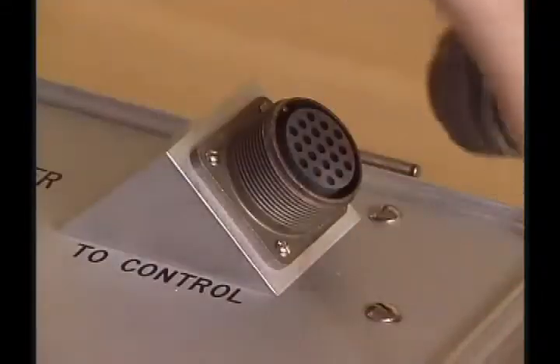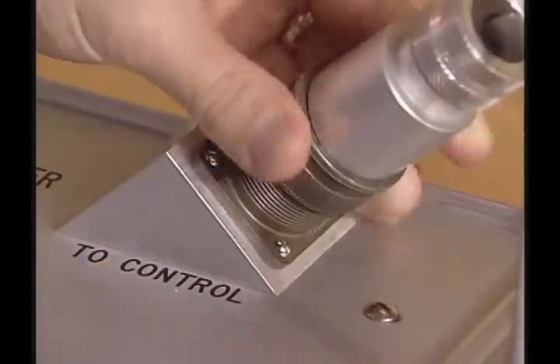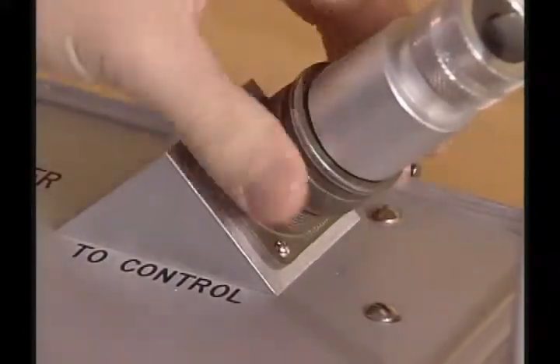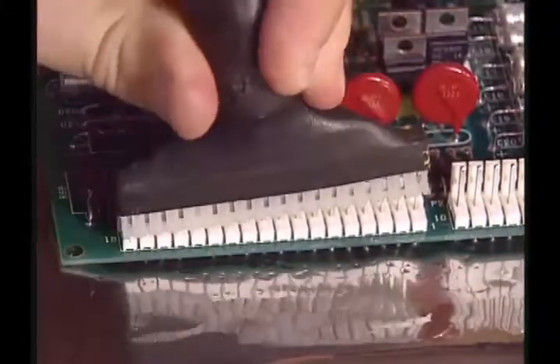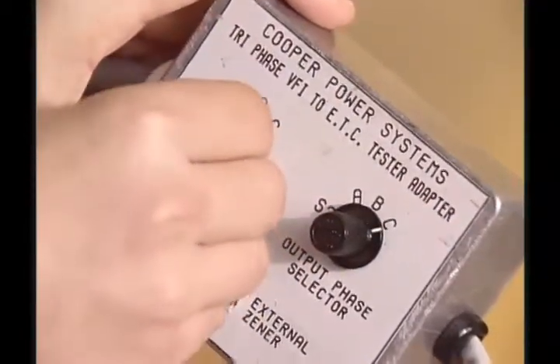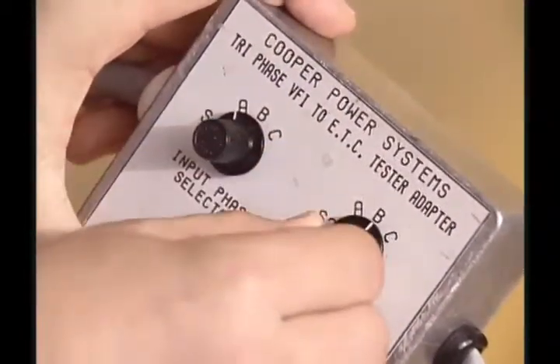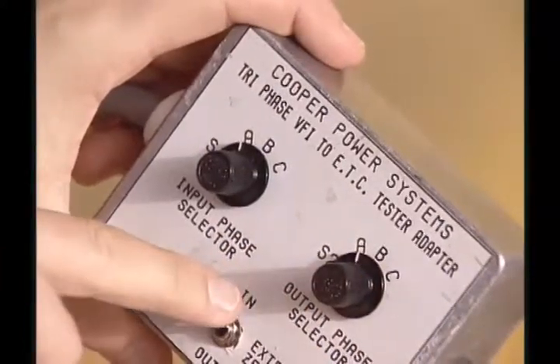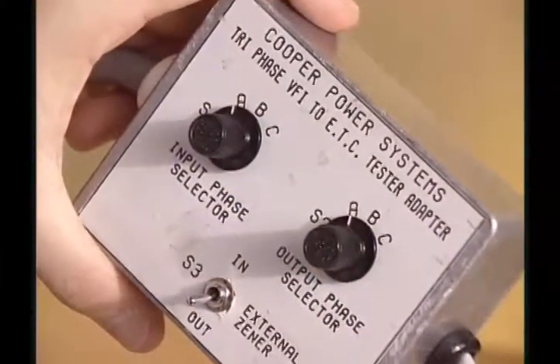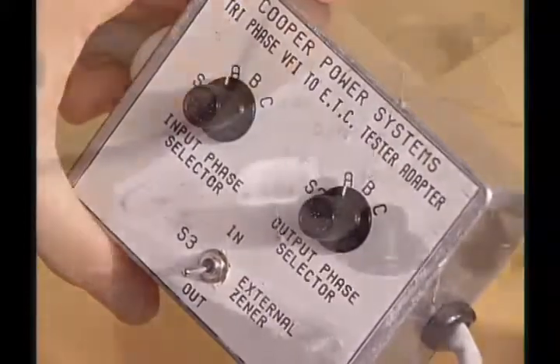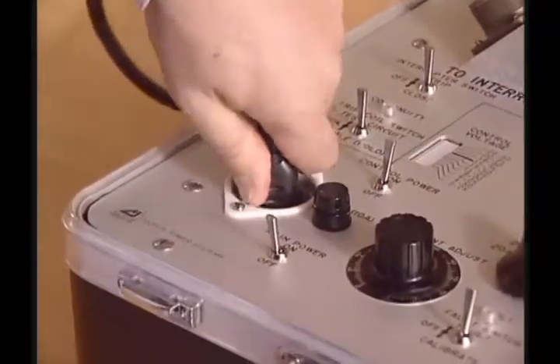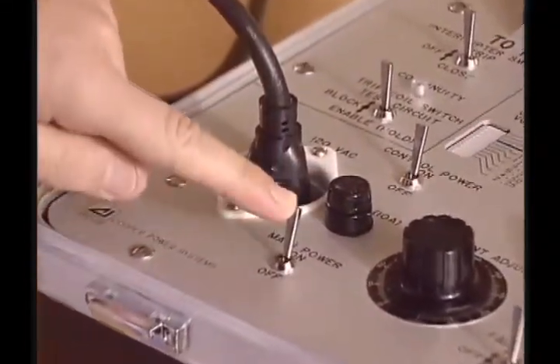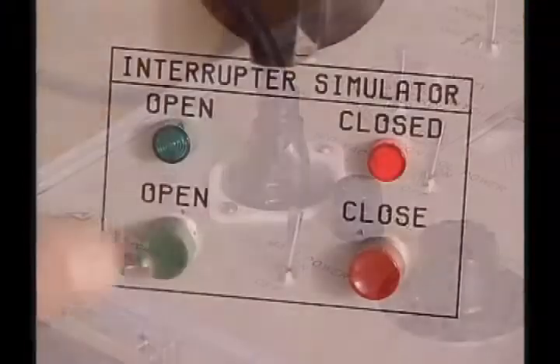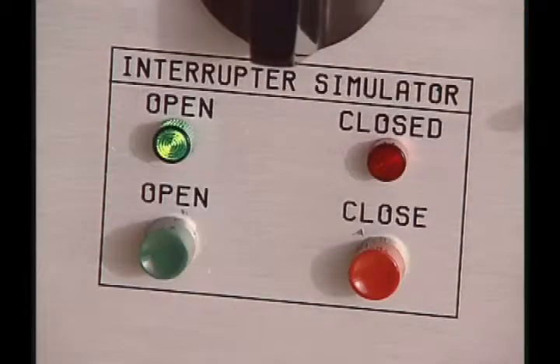To connect the circuit board to the tester, attach the adapter cable accessory between the connector labeled to control and pin connector P1 on the control circuit board. On the adapter cable accessory, set both the input and output phase selector switches to the A position. Set the external Zener switch to the out position. Now, connect the power cable and turn the main power switch on. After the power is on, be sure that the interrupter simulator is in the open position.